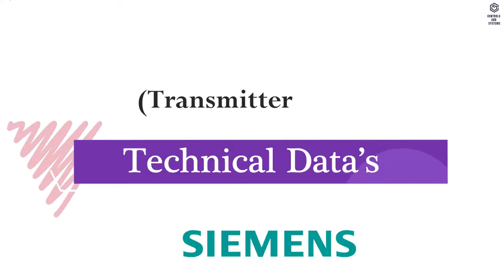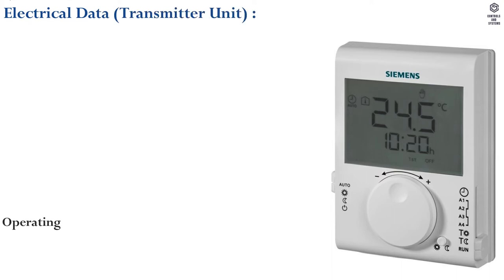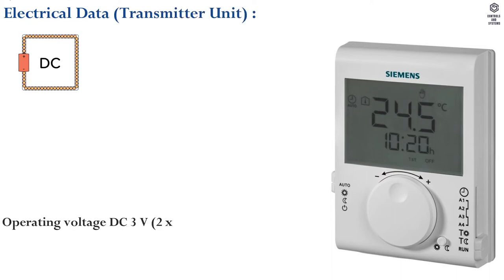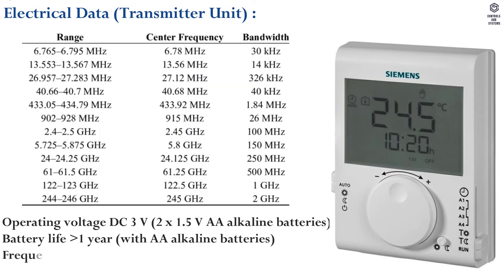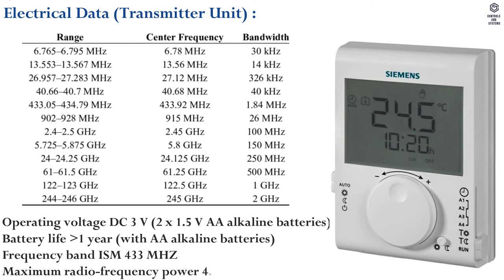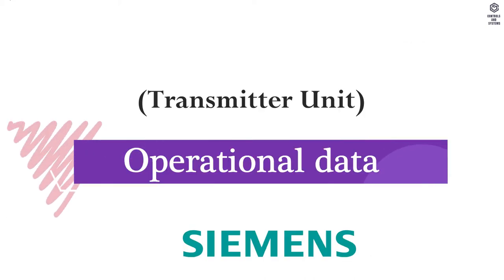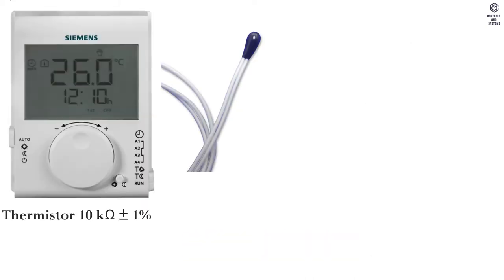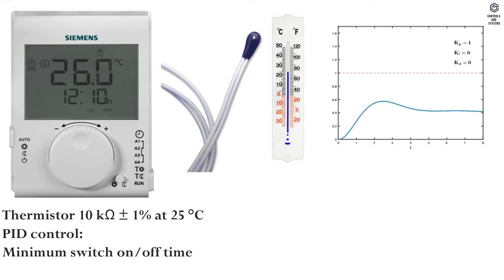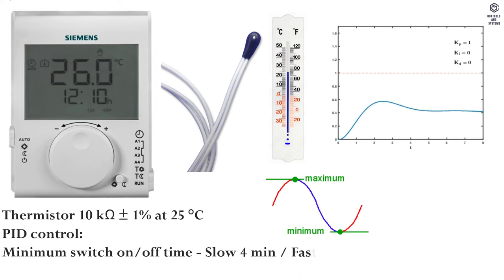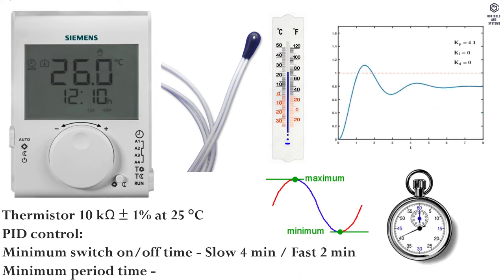Technical data for the transmitter unit. Electrical data: operating voltage is DC 3V using two 1.5V AA alkaline batteries. Battery life is greater than one year. Frequency band is ISM 433 MHz; maximum radio frequency power is 4.19 dBm. Operational data: thermistor is 10 kΩ ±1% at 25°C. PID control. Minimum switch on/off time: slow is 4 minutes, fast is 2 minutes.